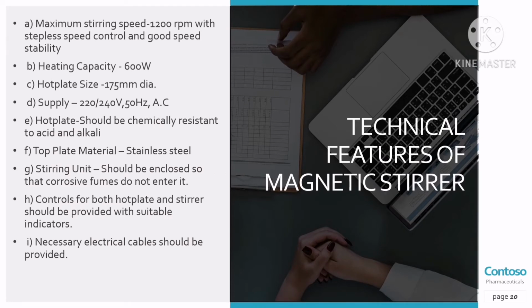Technical feature of magnetic stirrer. Basically, the magnetic stirrer must have a maximum stirring speed of 100 to 1000 rpm with stable speed control and good speed stability. Heating capacity must be 600 watt and hot plate size basically 175 millimeter. The supply must be 220 to 240 volt and 50 Hz. The hot plate should be chemically resistant to acid and alkali. The top plate material must be stainless steel.